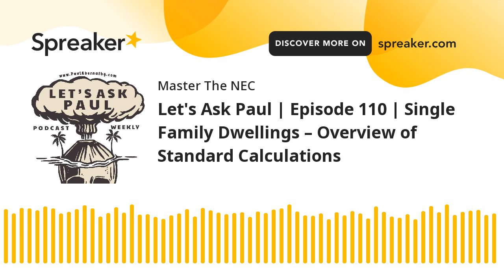In a single family dwelling, what you're going to do is look for your appliances that are fastened in place. And here's what it says. It shall be permissible. It's not required. It's a permissive rule. It shall be permissible to apply a demand factor of 75% to the nameplate rating load of 4 or more appliances rated a quarter horsepower or greater, or 500 watts or greater, that are fastened in place and that are served by the same feeder or service in the one family, two family, or multifamily dwelling. It says this demand factor shall not apply to household electric cooking equipment, clothes dryers, space heating equipment, or air conditioning.